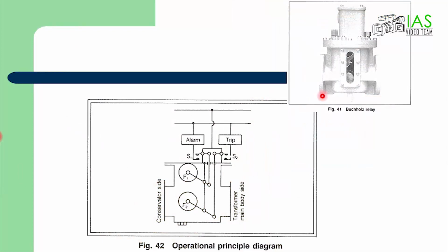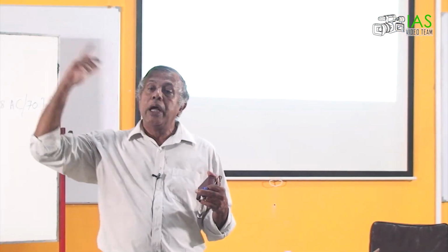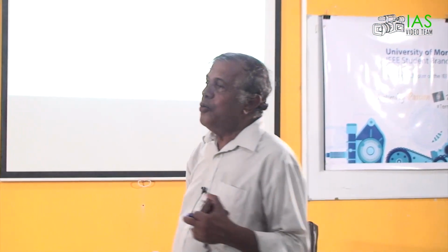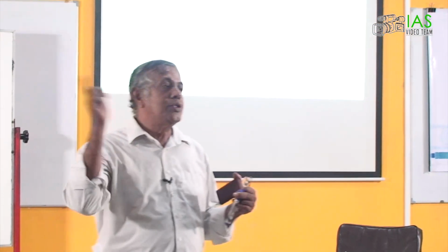Now, there are two incidents that can happen. If you have very low partial discharges, what happens is, partial discharges make gases out of transformer oil. So the gases slowly collect in this and actuate the top one, right? It actuates the top one and gives an alarm. Okay? Now, when the alarm comes, you can see the Buchholz relay alarm.